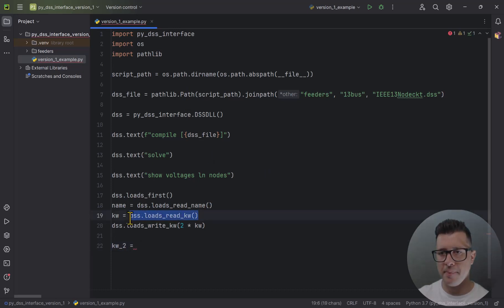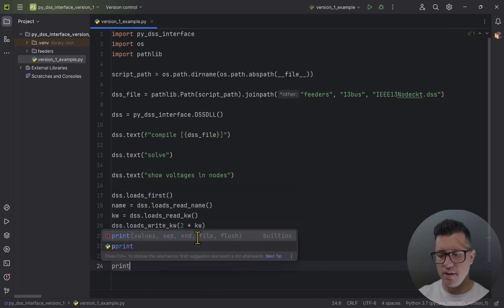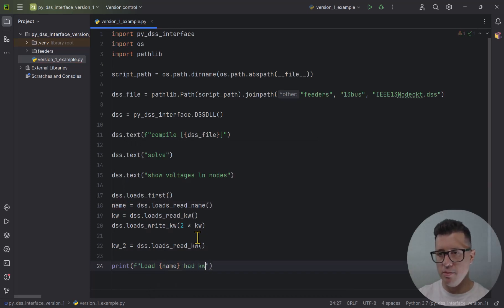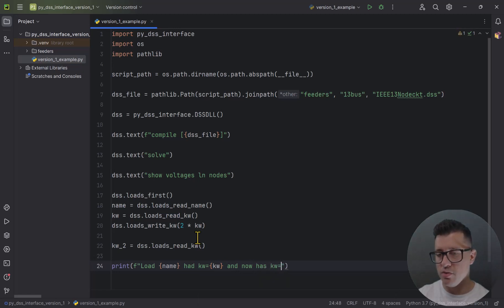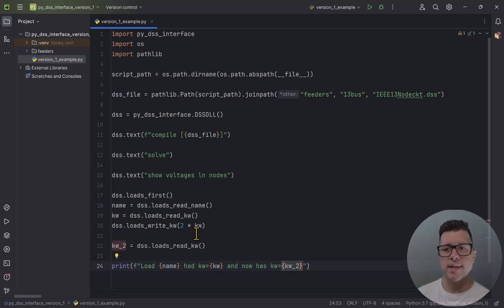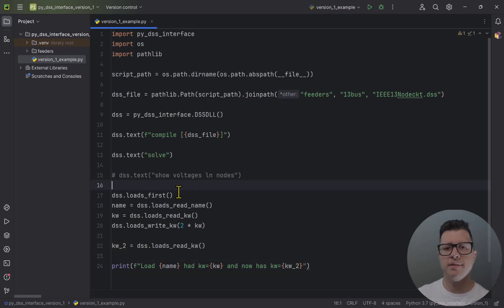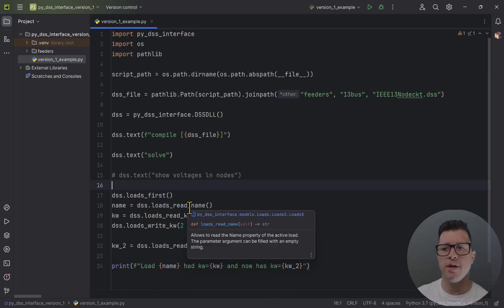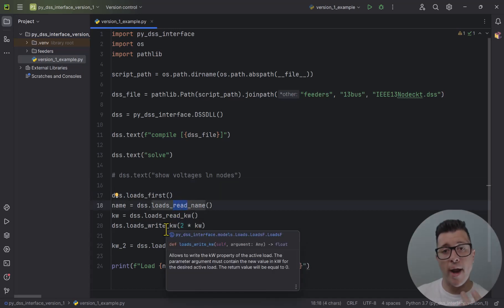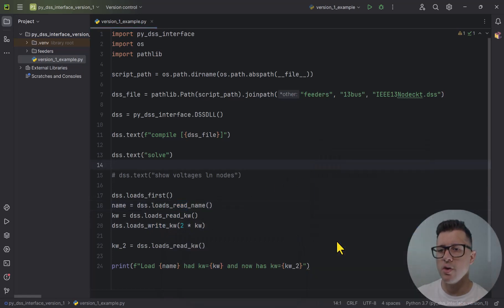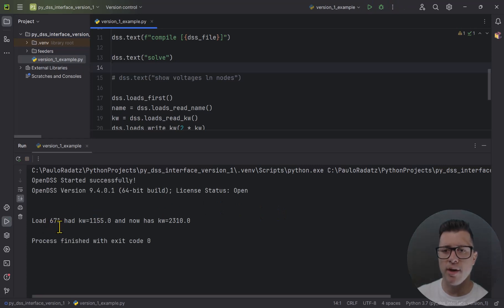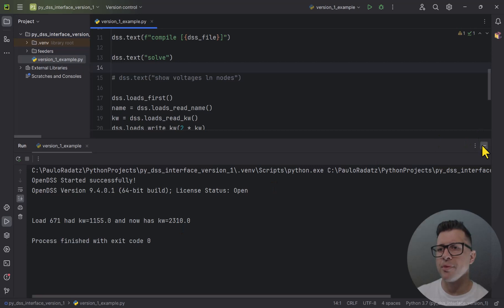I then read the new KW value and print the results: the load name, what KW it had, and what KW it now has. So to recap: I activated the first load, got its name and KW using the 'read' structure, changed it using 'write', and confirmed the change. When I run this code, I can see 'Load 671 had that KW and now has double that KW.' That's how you do things in version 1.